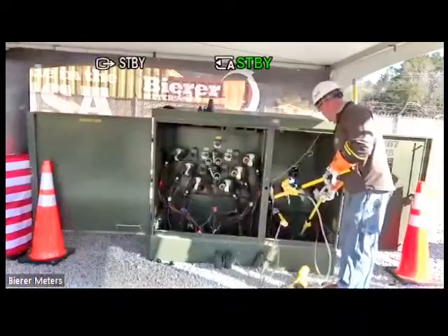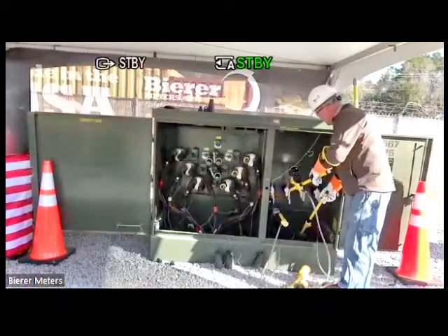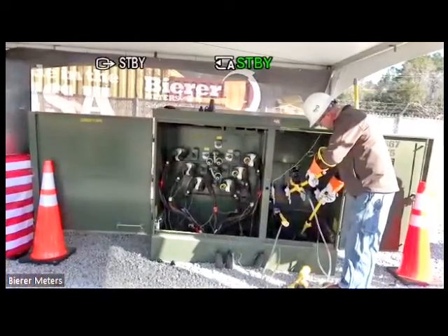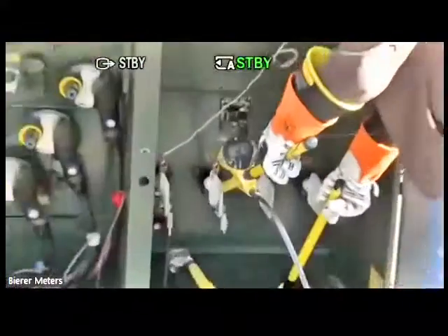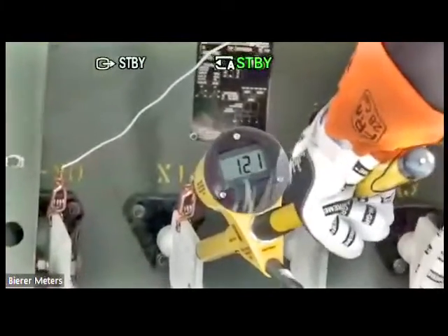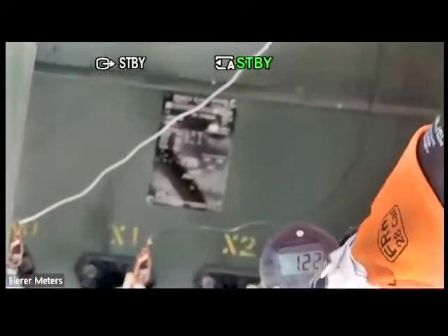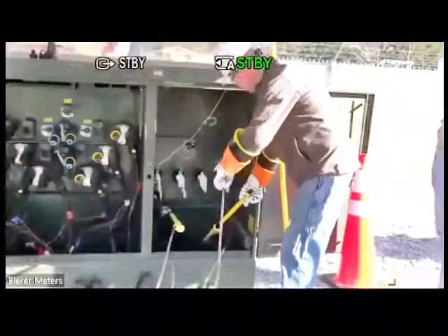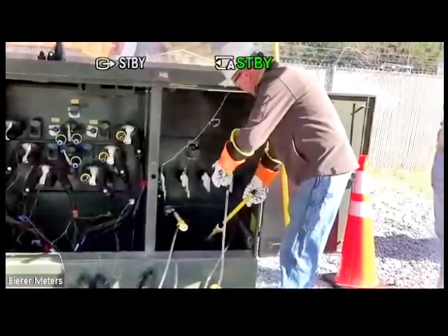So if I go to ground on here, get my X1, there's my 121 volts. Get Ryan to zoom in on that. Go to X2, my 121 volts again. Try to get my glove out of the way. Try not to rip my microphone off at the same time. And the X3.